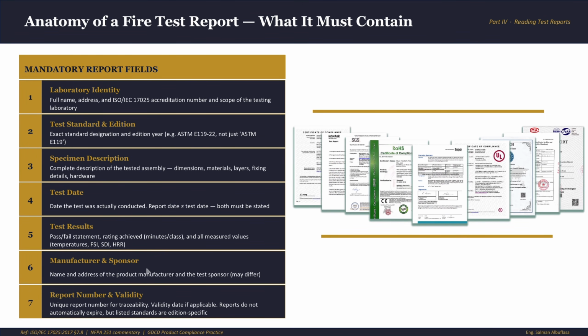And then the manufacturer and sponsor. They can be 2 different parties. Both must be stated and verified. And finally, report number and validity. Every report has a unique number. That number is how we trace it back to the lab, to the test, and to the product. So if someone cannot give us that number, I think we do have a problem.